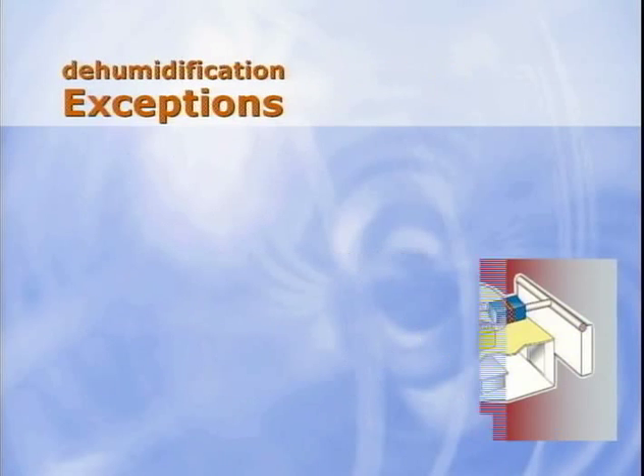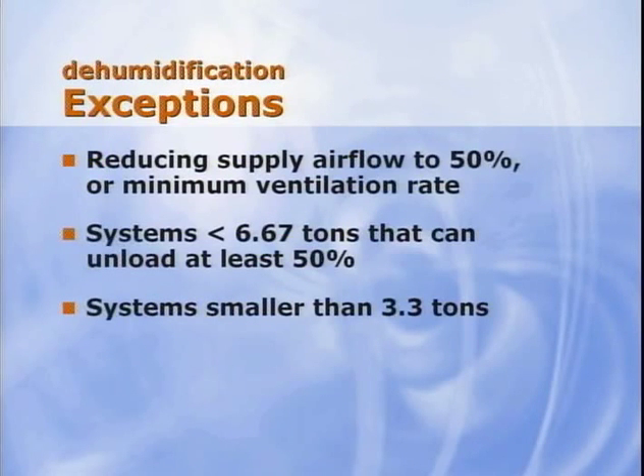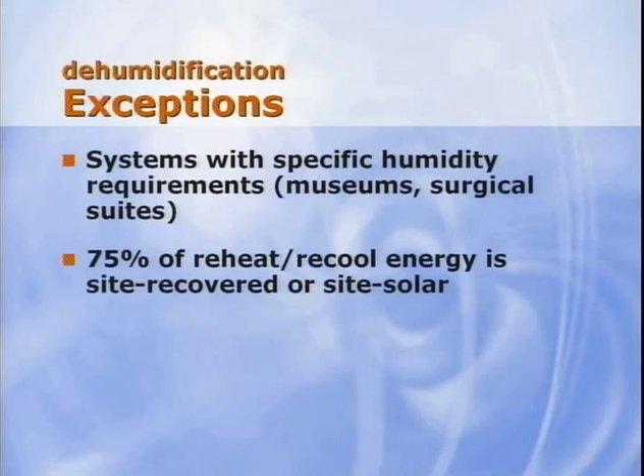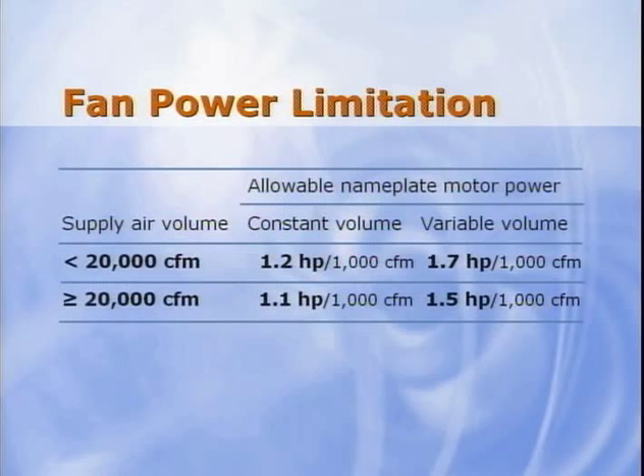In systems where active humidity control is being performed, there are different exceptions, but the thought is the same. Reduce system capacity prior to using new energy for reheat. Again, reheat may be used at any time if 75% of the reheat energy is site recovered or site solar. Later on, John will show us how this exception can be used in VAV rooftop systems. Once the fan system power exceeds 5 horsepower, there is a limitation on system fan power, and there are VAV fan control requirements.